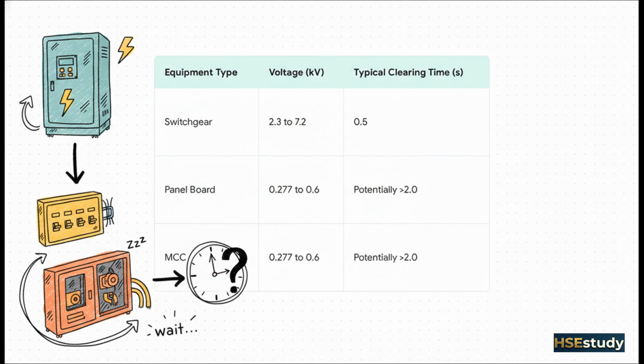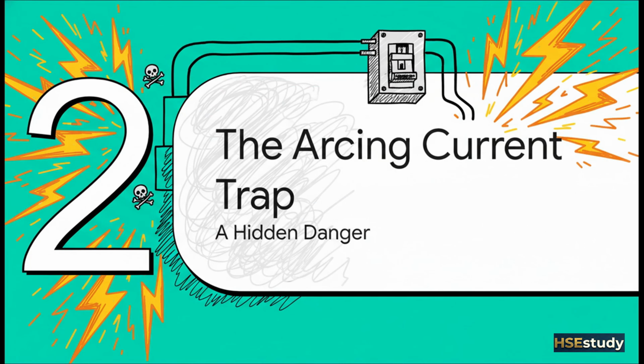Your medium voltage switchgear is engineered with some pretty sophisticated relays. They're designed to clear a fault in half a second, maybe less. But now look at the low voltage gear, the panel boards, the motor control centers. Their protective devices can take a staggering 2 seconds, or sometimes even longer, to trip. So why the massive delay? Well, that delay leads us right to something called the arcing current trap.